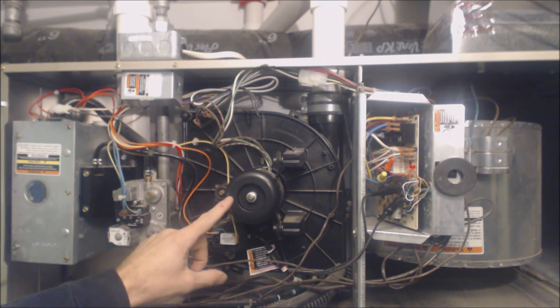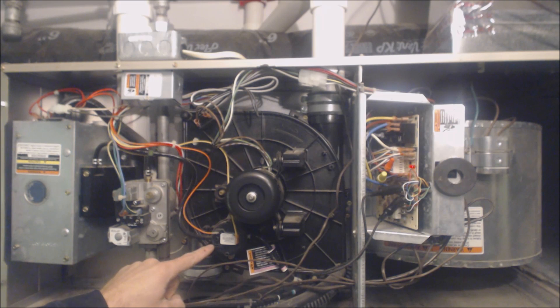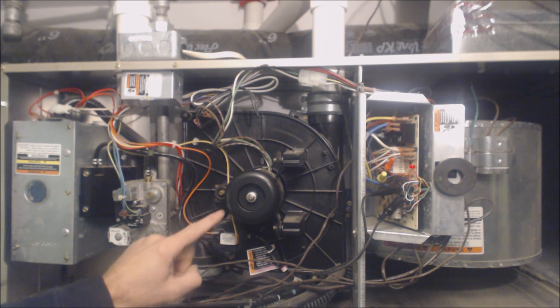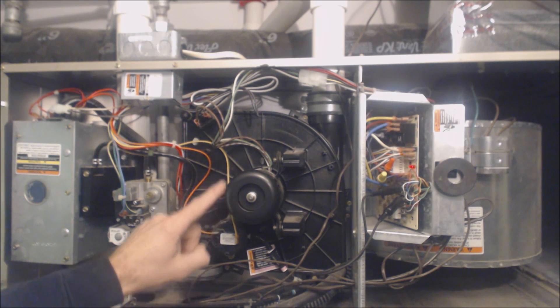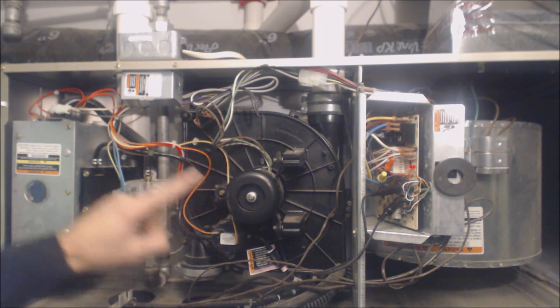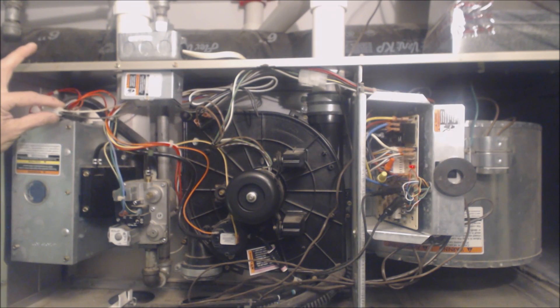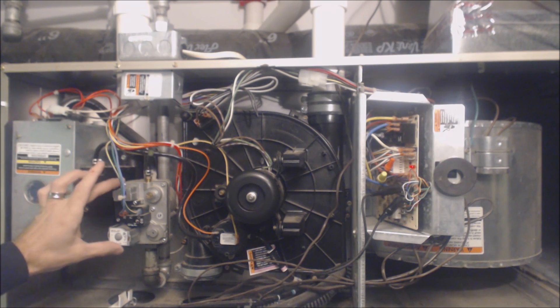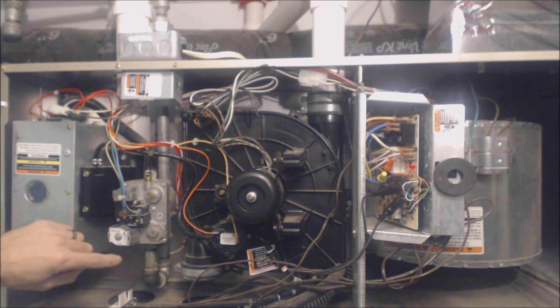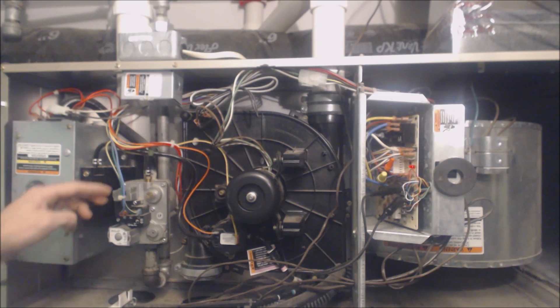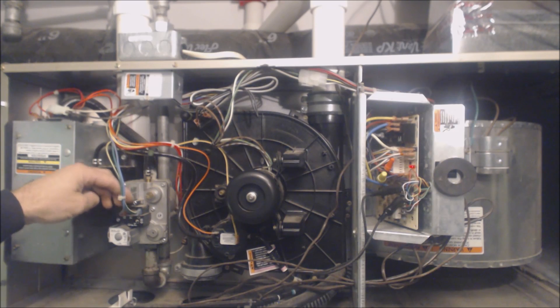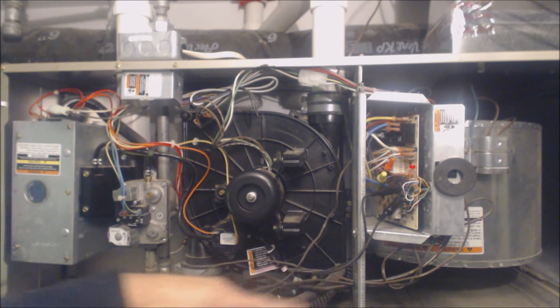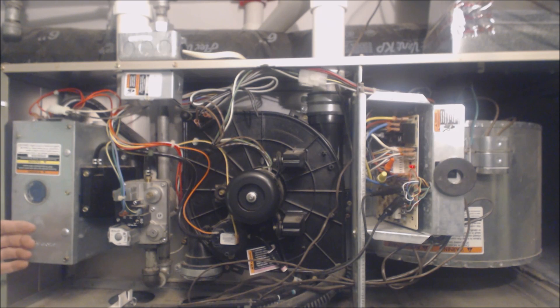You have the inducer motor turns on first. Then you have the pressure switch closes the electrical contacts proving that the inducer motor is running and nothing's blocking the exhaust pipe. After that, the hot surface igniter turns cherry red powered by 120 volts. Then the gas valve, the electrical gas valve lets gas through for three seconds. It's powered by 24 volts off of the control board. Then the flame occurs.